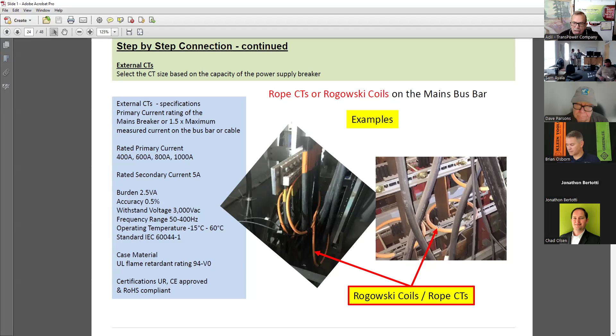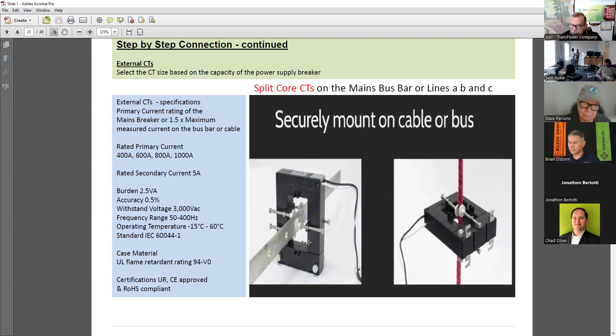And these have a special characteristic because I have seen on some of the chats projects, they bought these CTs, let's say they bought a 500 to 5 amp CTs, and on the side they realized that the peak currents are going to 600, 700 amps. Now they got to go buy those CTs again because they found that that CT won't do because the current is going up to 1000 amps. So what happens is when you buy one CT, install it and find out that it's not good, you got to go buy another CT. You can avoid such cases because this rope CT can handle up to 50,000 amps going through this bus bar. That is the reason why we have standardized all installation.